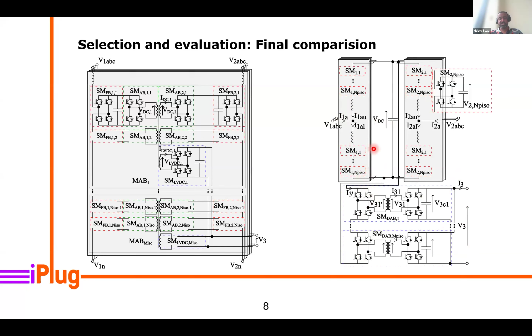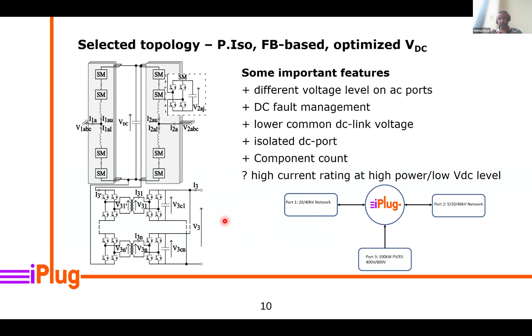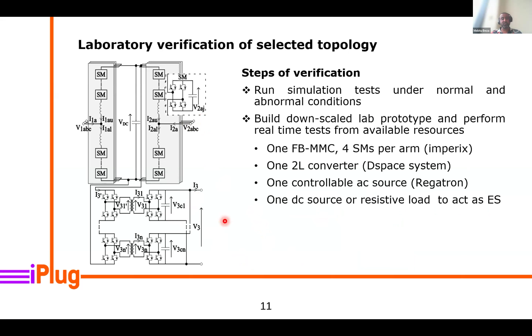The application is medium voltage, but our lab tests were done at lower voltage, while still realizing different voltage levels on the two AC ports and a DC port connected to a DC load. We used resources at Chalmers: on one port, a multi-level converter with an MMC system with 4 sub-modules per arm, 8 sub-modules per phase, using full bridge cells, with an optimal DC voltage level for the design. On the other AC port, we use a 2-level voltage source. The DC sides of these two converters are coupled to make a back-to-back configuration, and with the DC voltage level and the multi-level converter using full bridges, we can decouple the voltage realized on each port.